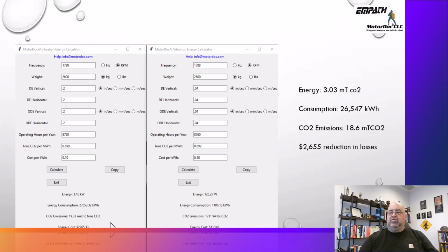But then it will show me the difference in cost associated with that defect. And that I can use to show my return on investment for, say, a proper balancing job or proper alignment. And I can make a statement that we're going to reduce 3 metric tons of CO2, we're going to reduce 26,000 kilowatt hours. So when I take the kilowatts, that converts to this and $2,600.